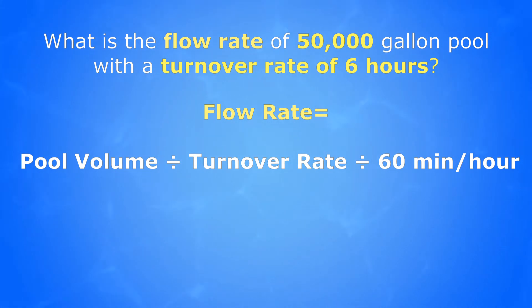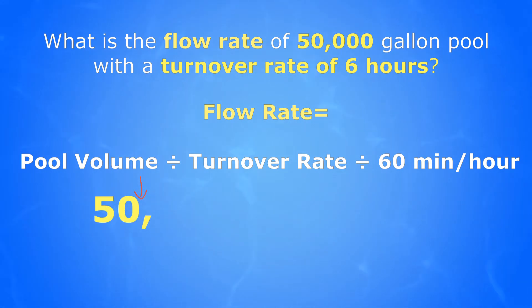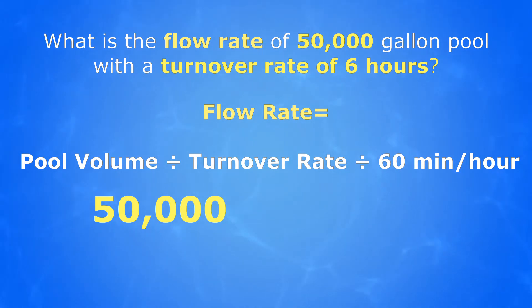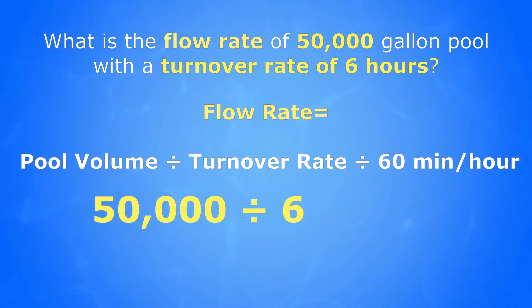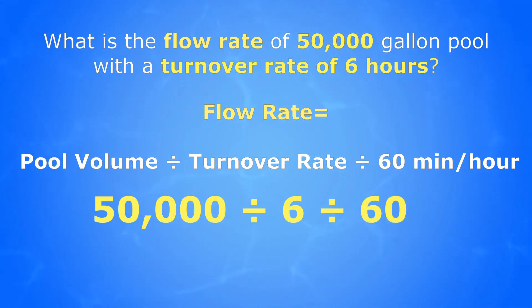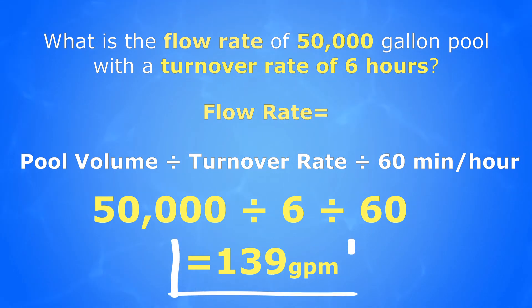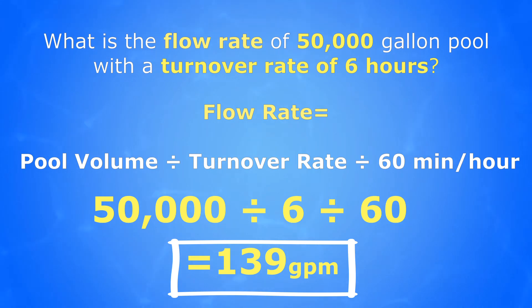So let's go ahead and fill this in. Our volume is 50,000 gallons, so that would go right here. Divided by our turnover rate, which in the problem is six hours. And then we divide that by the 60, which is part of the formula. If we calculate all that out on our calculator, you would get an answer of 139 gallons per minute. And that would be the flow rate of this 50,000 gallon pool.